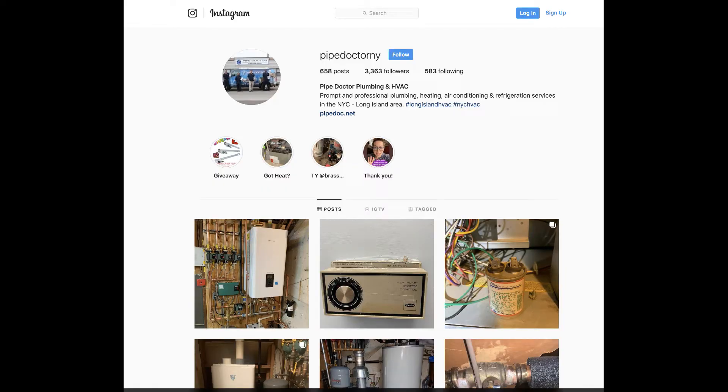Hey, what's going on everyone, this is Mike from The Pipe Doctor. In this video we are removing a Burnham P206 six-zone gas-fired boiler with a Laars indirect water heater. This Burnham P206 was misdiagnosed by another contractor who then brought in a chimney company, but it's completely carbonized. Because of the age — 21 years old — and the likelihood of future expensive repairs, the homeowner decided to replace it with a brand new system.